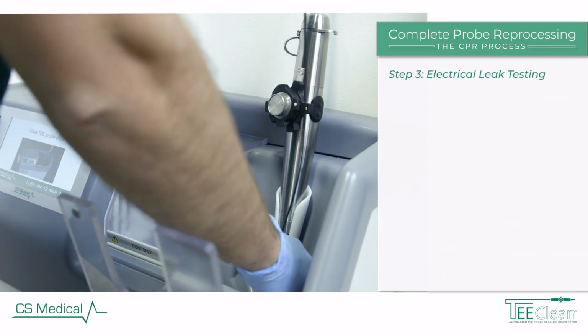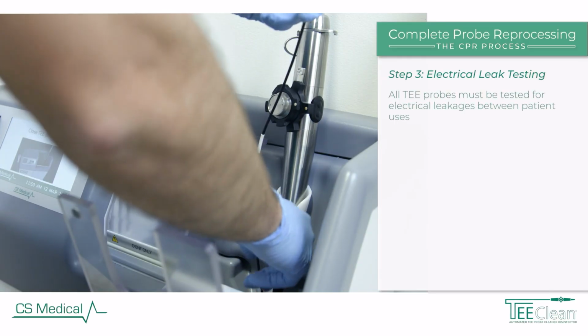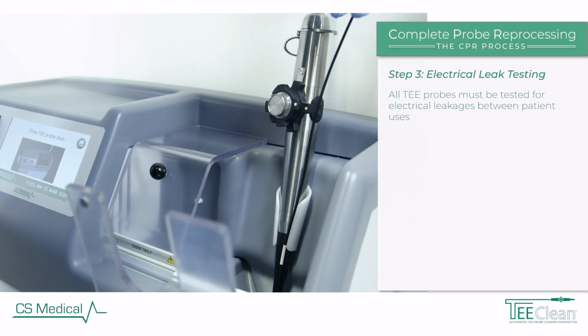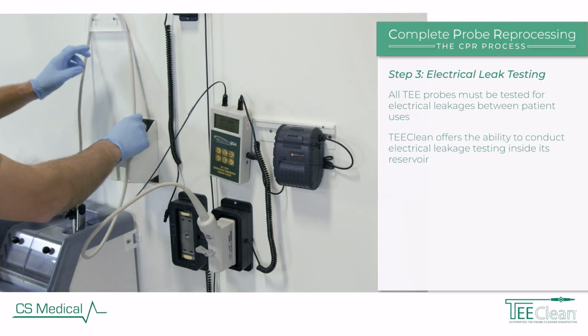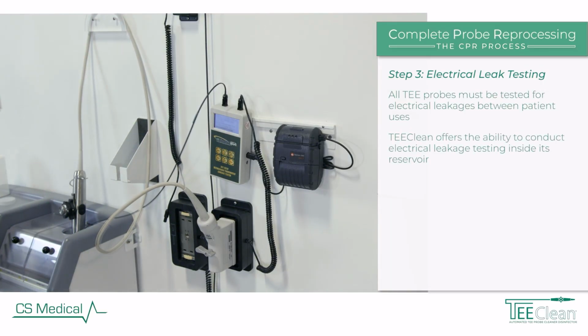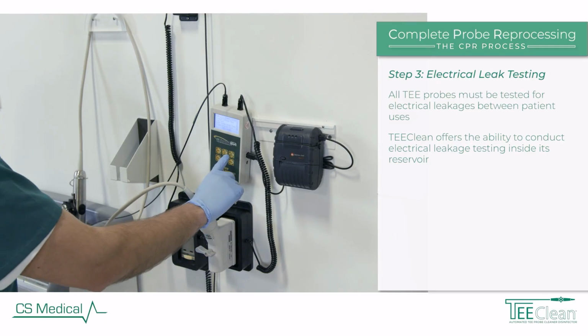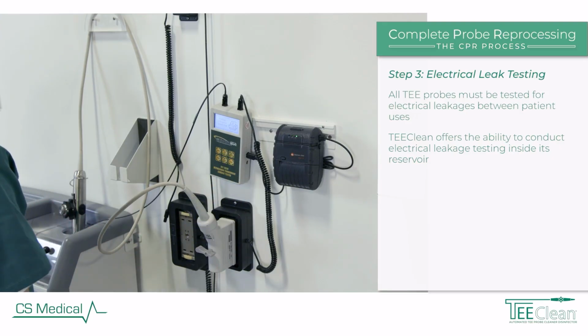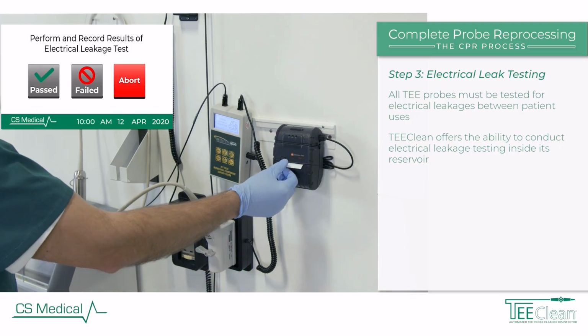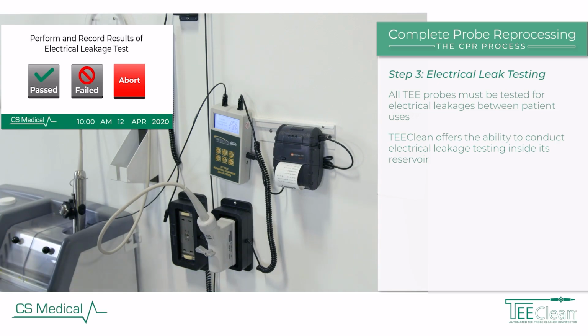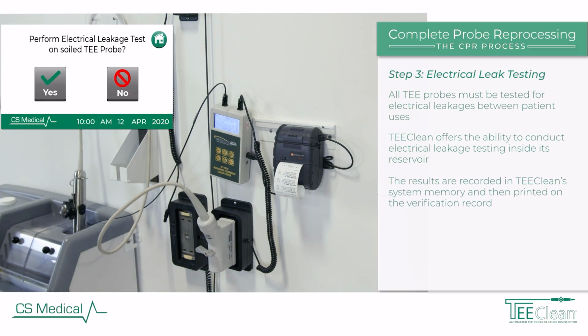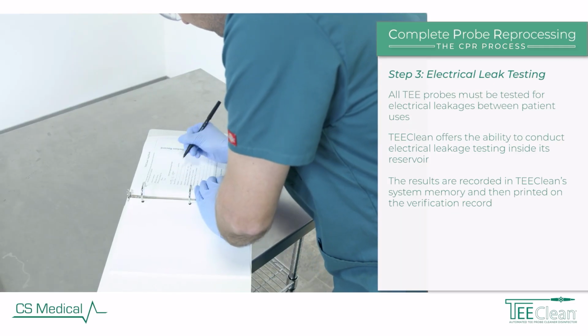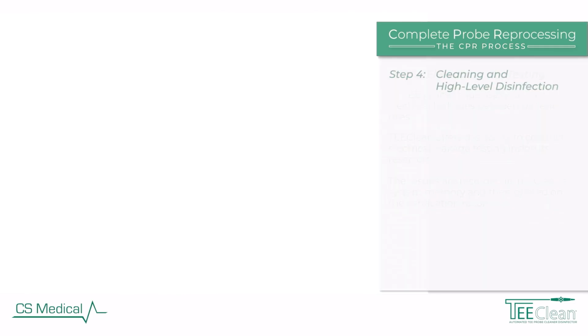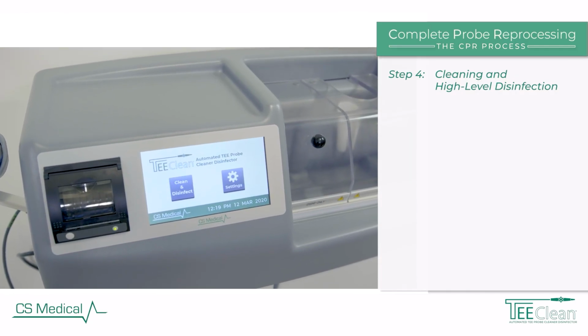Step 3. Electrical leak testing. All TEE probes must be tested for electrical leakages between patient uses. TEEClean offers the ability to conduct electrical leakage testing inside its reservoir, minimizing the need for additional containers to accomplish this requirement and reducing probe handling that could result in damage to the transducer. TEEClean provides prompts for completion of electrical leakage testing. The results are recorded in TEEClean system memory and then printed on the verification record for storage in the TEEClean logbook.